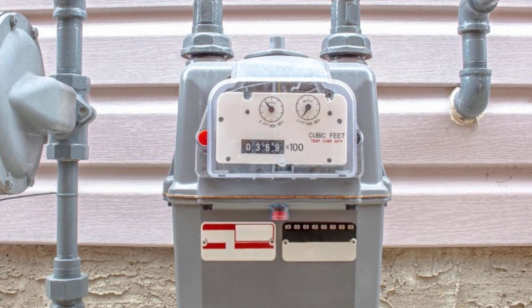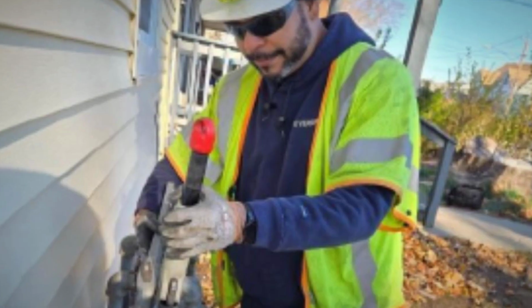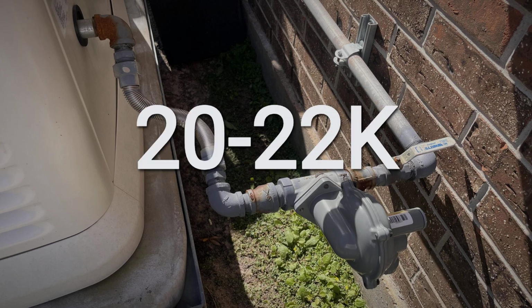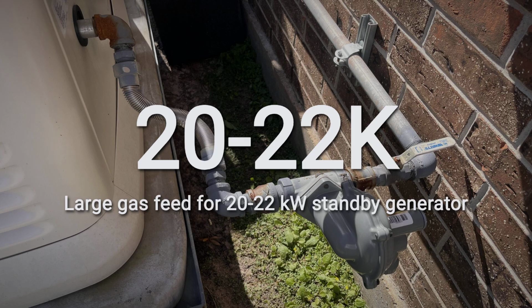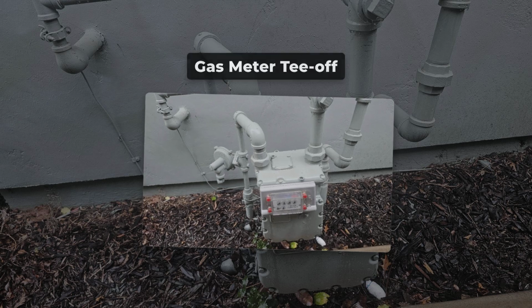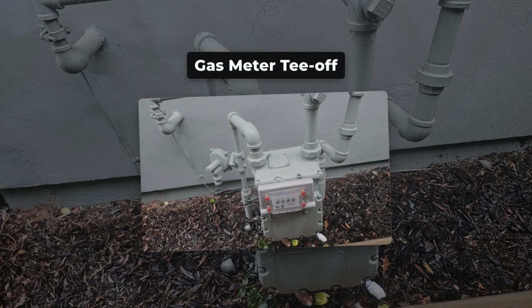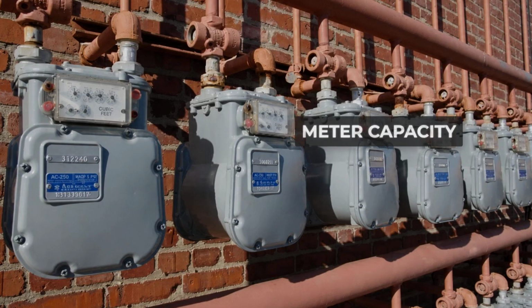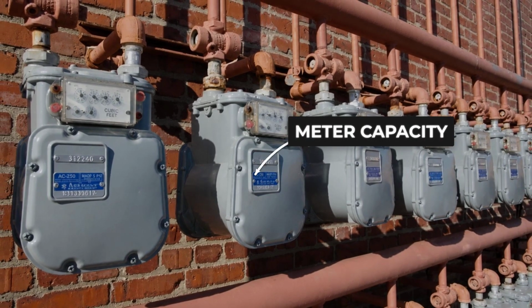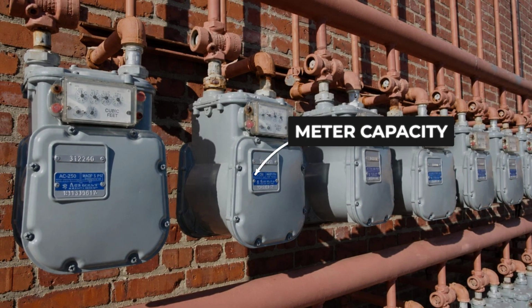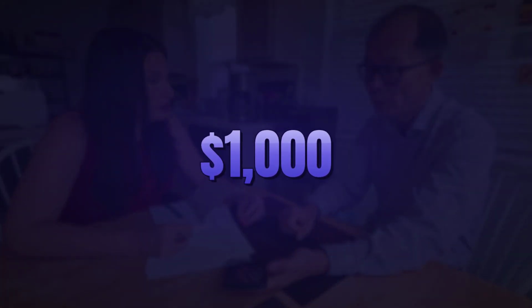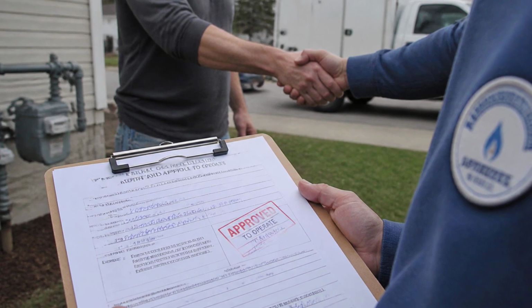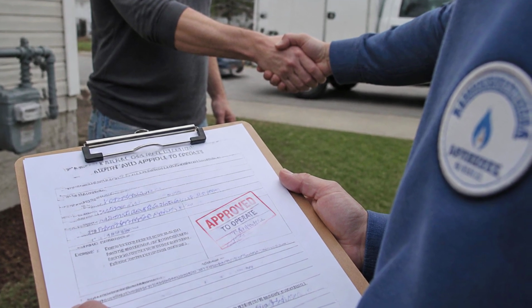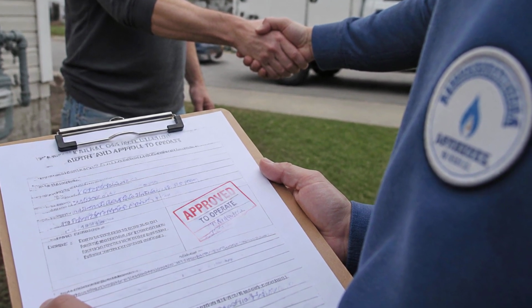One real cost that does belong on this list, and isn't padding, is a gas meter upgrade. A 20 to 22 kilowatt unit needs a decent-sized supply line and a meter that can feed the generator and the house at the same time. If your existing meter genuinely can't handle that combined load, a meter upgrade running around $1,000 is a legitimate charge, not a scam, and your utility usually has to sign off on it either way.